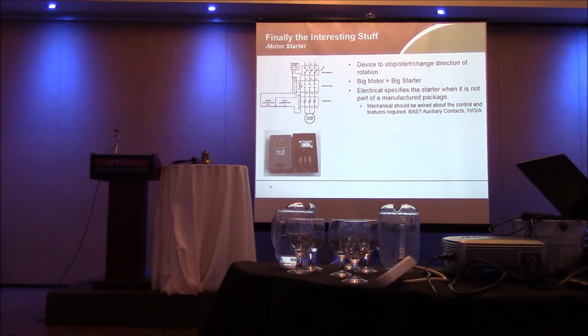Control features. Oh, man. I'll bet you this is launching more change orders than anything else. Especially where electrical has specified the starter and mechanical's thinking they're getting something and they're not getting it. They're not getting a run contact that tells them the contactor's closed, the motor's running. They're not getting an overload indication contact to say that, hey, it tripped on overload.